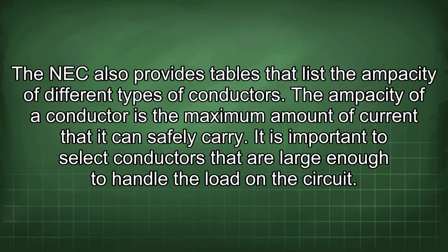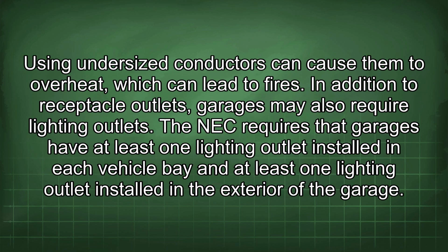The NEC also provides tables that list the ampacity of different types of conductors. The ampacity of a conductor is the maximum amount of current that it can safely carry. It is important to select conductors that are large enough to handle the load on the circuit. Using undersized conductors can cause them to overheat, which can lead to fires.